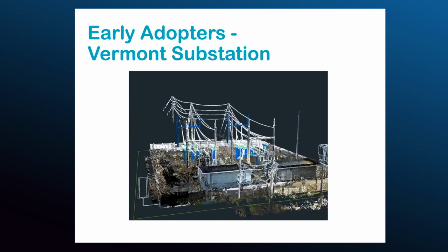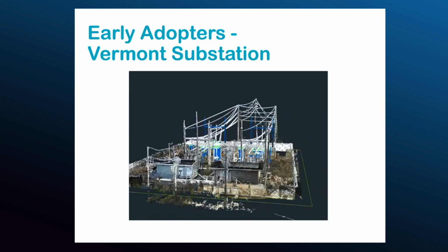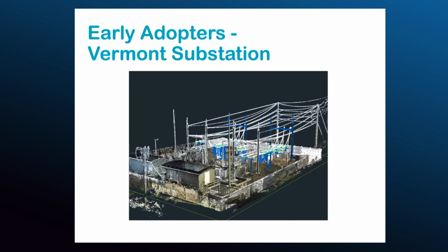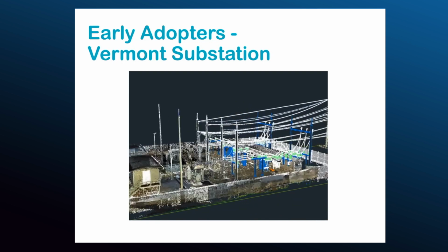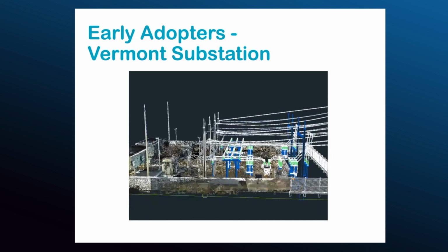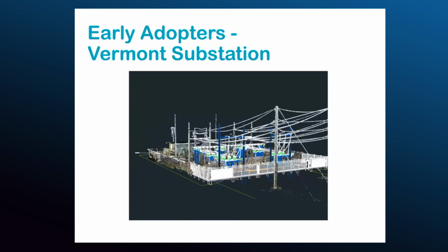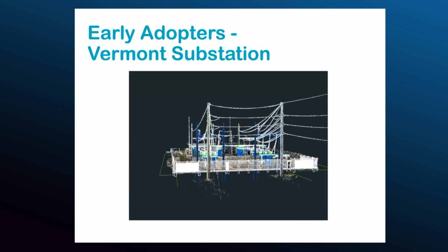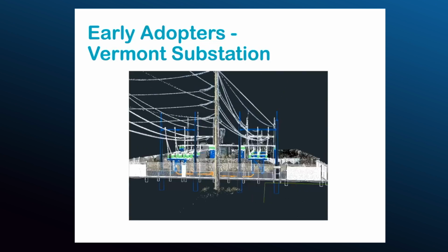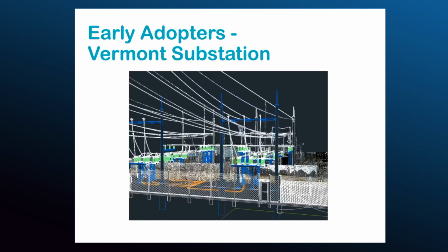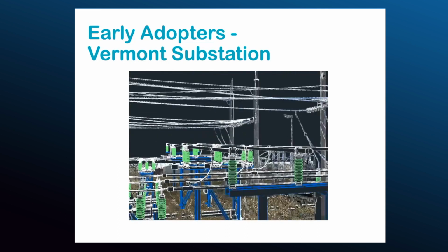The site here is a large mine connection. This was a customer project, where it's a little bit hard to see with the slow rendering of the point cloud. But effectively, we've had to extend our yard 10 meters out in front of the site there and build out some 66 kV bays underneath some live conductors. So this was a pretty large undertaking.